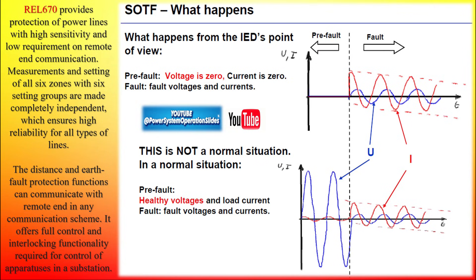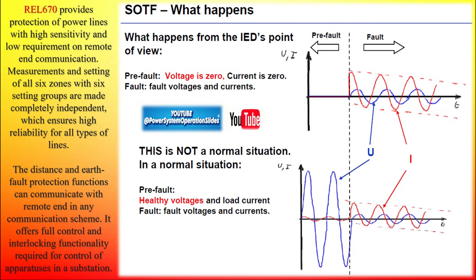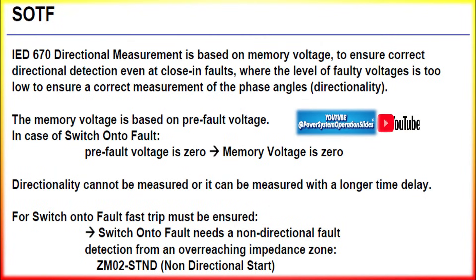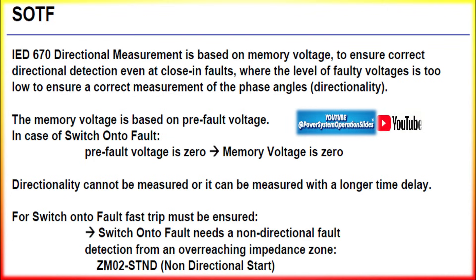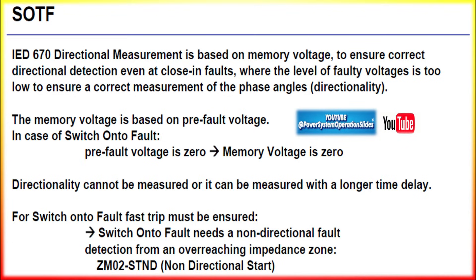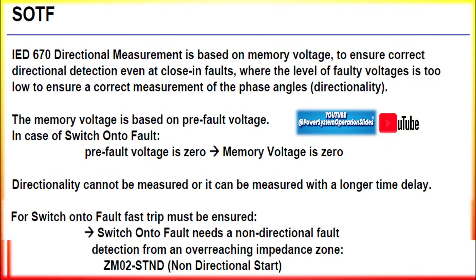In traditional distance protection schemes, the relay measures the impedance of the transmission line between itself and the fault. Different zones of protection — Zone 1, Zone 2, Zone 3 — correspond to various portions of the line. Zone 1 is typically instantaneous and protects 80 to 90 percent of the line. Zone 2 protects the remainder with some time delay. Zones 2 and 3 have time delays to ensure selectivity, so the nearest breaker operates first. However, with SOTF, the delay mechanisms are bypassed to provide instantaneous tripping, ensuring the fault is cleared without waiting for impedance zones to determine the fault location.